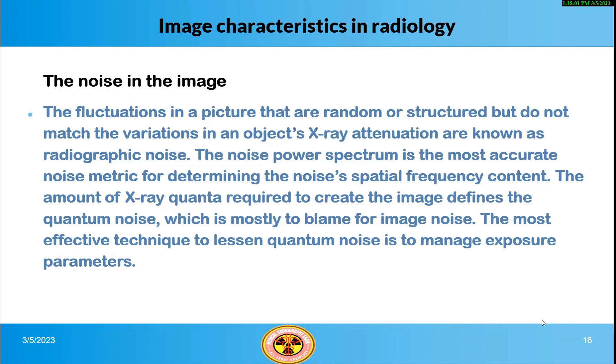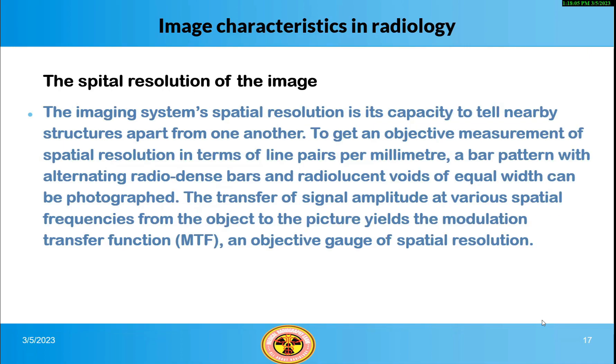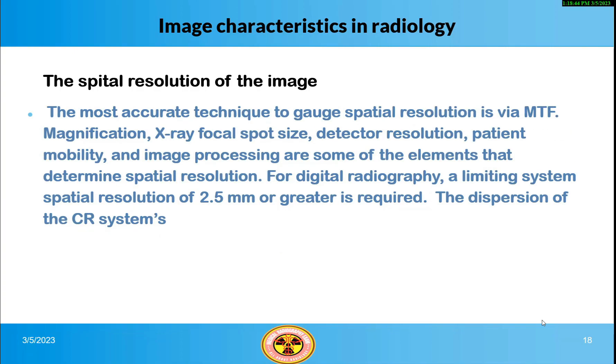The most effective technique to lessen quantum noise is to manage exposure parameters. The imaging system's spatial resolution is its capacity to tell nearby structures apart from one another. To get an objective measurement of spatial resolution in terms of line pairs per mm, a bar pattern with alternating radiodense bars and radiolucent voids of equal width can be photographed. The transfer of signal amplitude at various spatial frequencies from the object to the picture yields the Modulation Transfer Function (MTF), an objective gauge of spatial resolution.